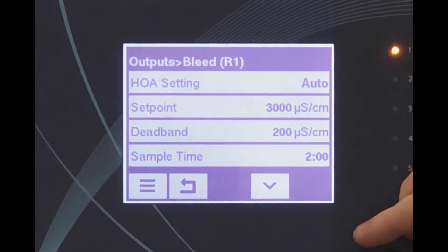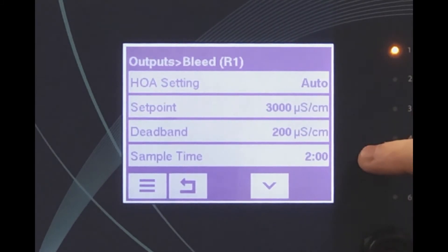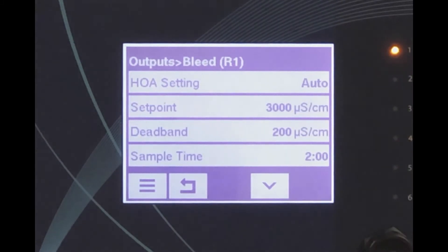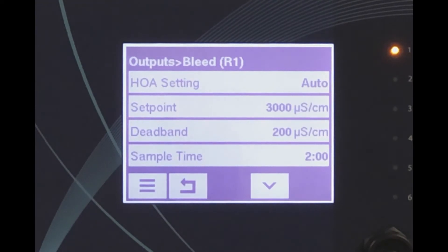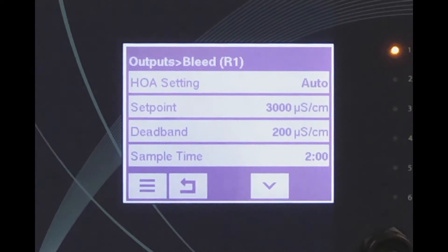For this setup, we need to program a sample time — the amount of time the valve is open to take a sample. It's important that this amount of time be long enough for the water in the drum of the boiler to reach the sensor and for the sensor temperature element to accurately read the temperature, generally around one to two minutes for this blowdown method.